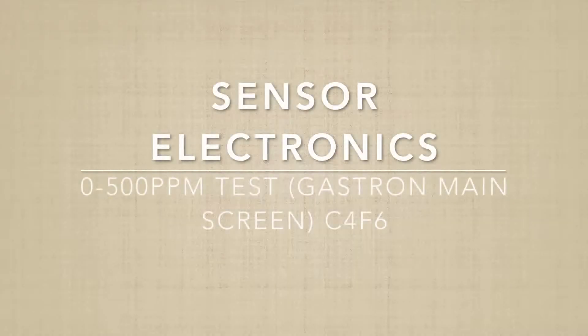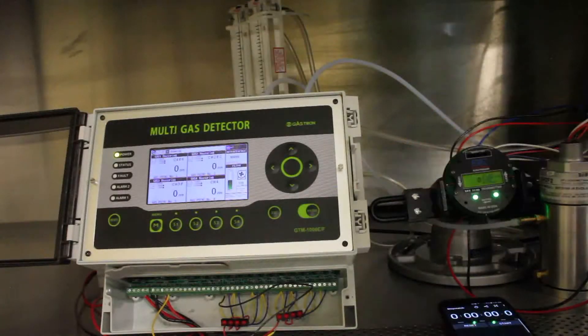This is a 0–500 ppm C4F6 test. We'll be running the units in series using the Gastron unit as a sample draw, and it'll be pulling the sample through the SCC5000 unit, so both units will be seeing the exact same gas.